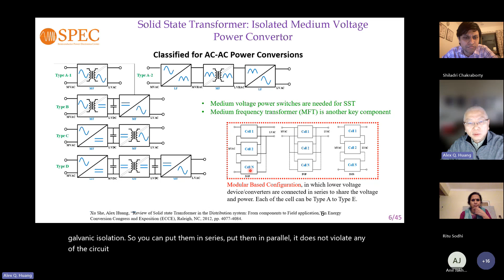One challenge is typically the AC side is very high voltage—here we show everything AC, because the legacy AC is medium to very high voltage. Semiconductor technology does not support very high voltage at the moment, although that's one direction we want to go. One way to handle it is to put several converters in series, because with galvanic isolation you can put them in series or in parallel without violating circuit connection constraints. Input series, output parallel is one popular way to increase voltage on the medium voltage grid side. So the important technologies are semiconductor devices, topology, and the transformer we call a medium frequency transformer—I'll show why we don't call them high frequency.